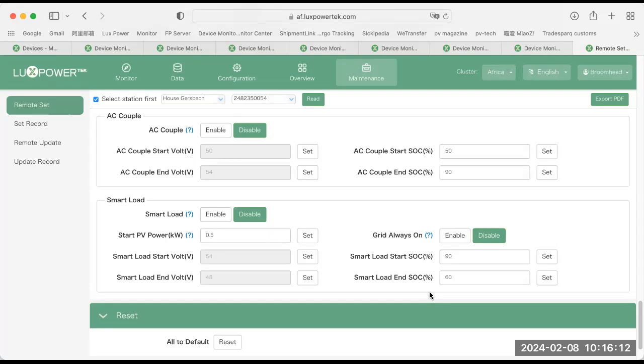Yes. Yeah. Because when you enable it, this one, the grid always on, it means that if the ESCOM is on, it will always use the excess power to power the smart load, which is not necessarily the case that they want. Okay. So disable that.